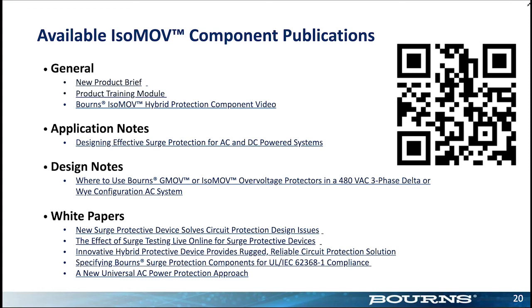Another question that came in is, the IsoMOV spec table that you showed didn't include max energy measured in joules, which commonly pops up in MOV data sheets. Is there a reason for that? Typically we didn't consider that, but there was no reason that we didn't put it on. A lot of customers don't really ask about the joule rating. They're more asking about the I nominal, which is basically what the UL spec asks for for any kind of SPD device. So we just focus on that.